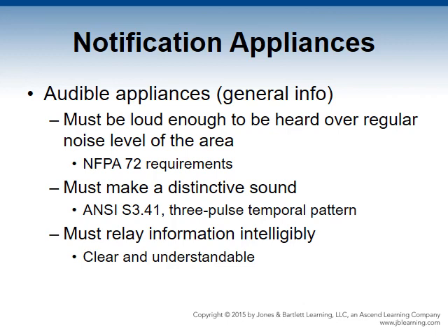NFPA 72 requires an evacuation signal to be in accordance with ANSI S3.41, the American National Standard Audible Evacuation Signal, which is a 3 pulse temporal pattern. It repeats for as long as it takes to evacuate the building, no less than 180 seconds.